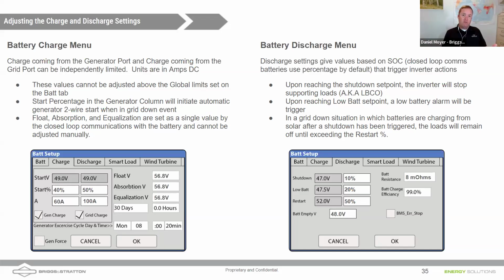While the generator is running, all of the loads would also be satisfied as well. The grid charge, if grid is there, I have it set to charge at 100 amps, and the grid would start to recharge the battery at 50% here. All of that float, absorb, equalize is all auto-populated by the battery. You can program in some default values before you connect closed loop communications so that if ever closed loop communications is lost, those values will revert back to the defaults that you put in there. But you'd only be able to do that if there's no closed loop comms. Just understand that those will all be auto-populated as well.